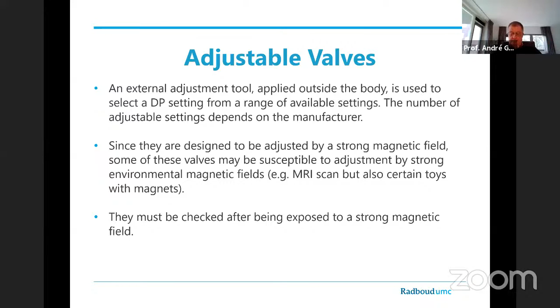These adjustable valves still have a siphoning effect. They are differential pressure valves, so they just react to the difference between proximal and distal. And if it sucks out, so if the distal is negative, then you get this siphoning effect. And therefore you need either a compensating mechanism for gravity or an anti-siphoning mechanism.